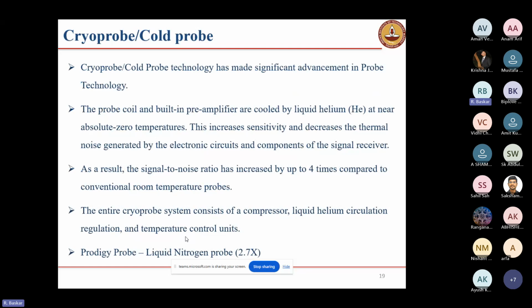The third one is that nowadays these cryo probes are very expensive, but they introduced the cryo or cold probe technology, which has made a significant advance in probe technology, because the probe coils have the preamplifier and all the electronics built in, all cooled with liquid helium. It will increase the sensitivity. So this increases the signal intensity 4 times. When we have a small amount of compound, the cryo probes help more.